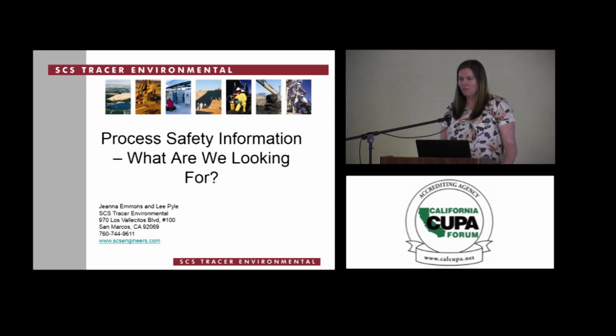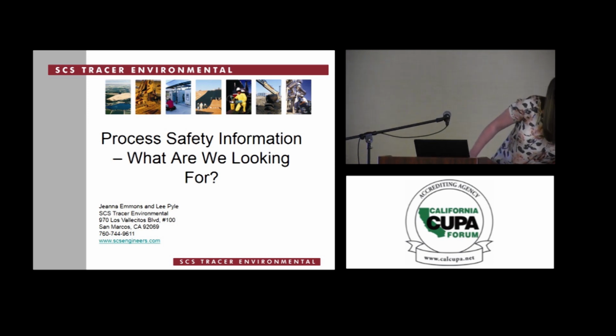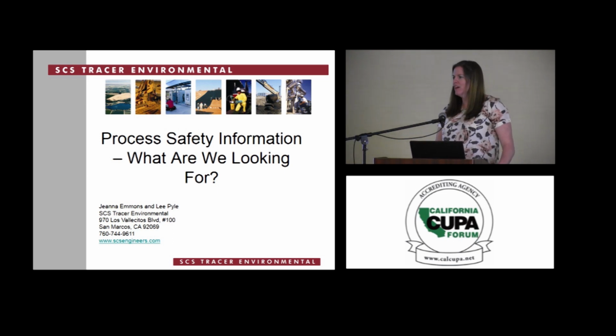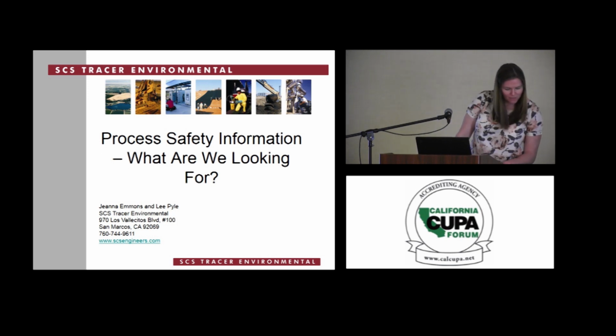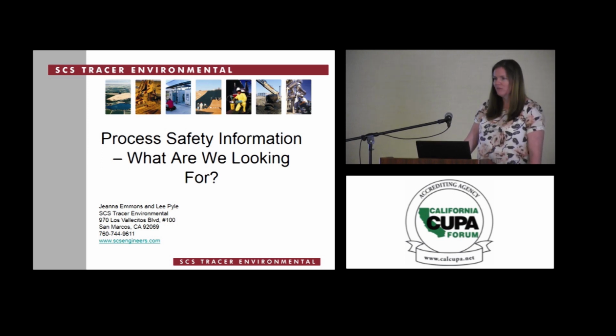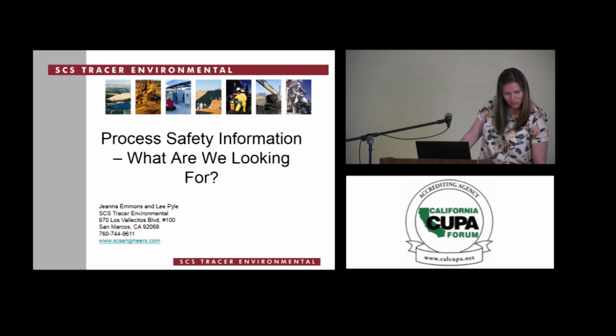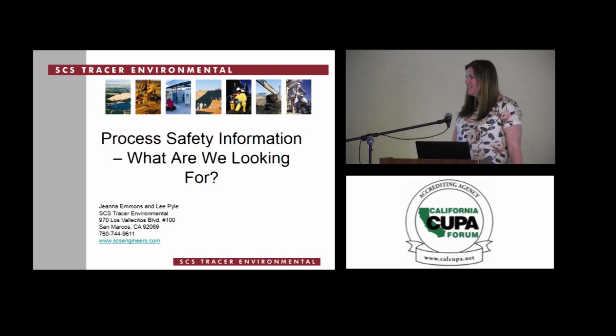Let's see. Process chemistry, I think that might be in there. Go to page 3-1. Now, if they followed through with the instructions provided by their corporate company, they would have more info, but they really didn't have any of this on site. Let's see. Where's the next list? Materials of construction. See any of that? They do ask for, there was an insert, I believe, for IIAR forms. So that's a positive. But it was blank. So not very helpful. Relief system design and design basis. Any mention of that?